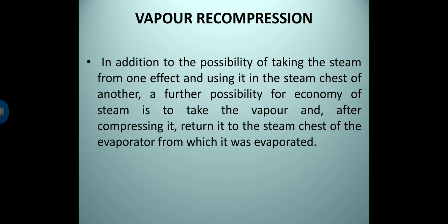The next one is vapor recompression. In addition to the possibility of taking the steam from one effect and using it in the steam chest of another, a further possibility for economy of steam is to take the vapor and, after compressing it, return it to the steam chest of the evaporator from which it was evaporated.